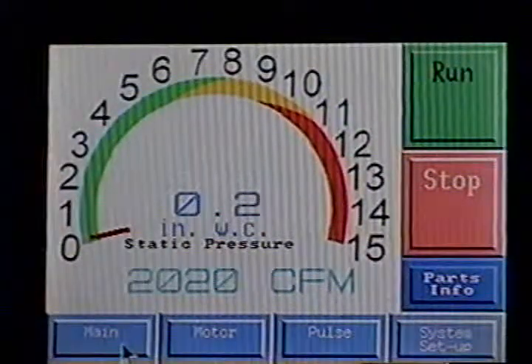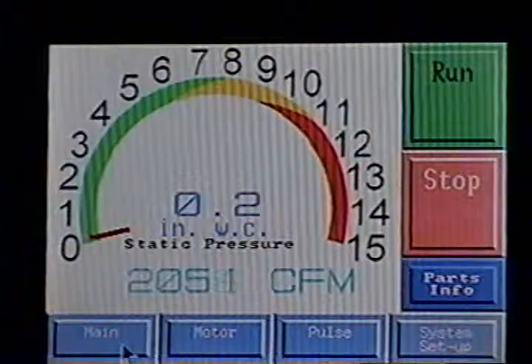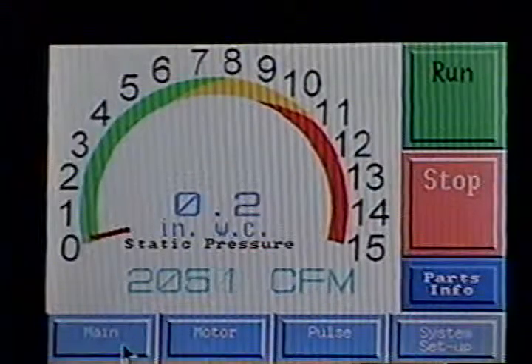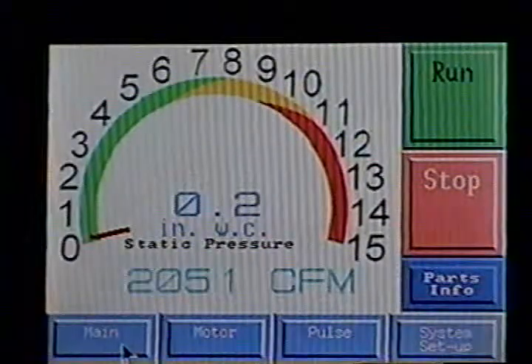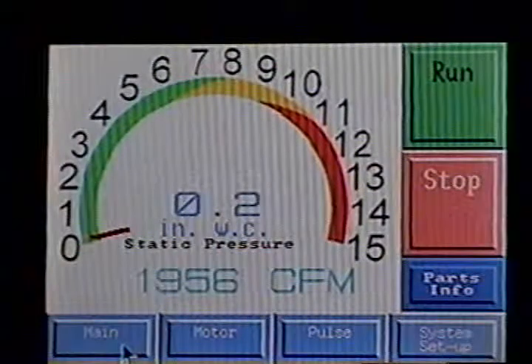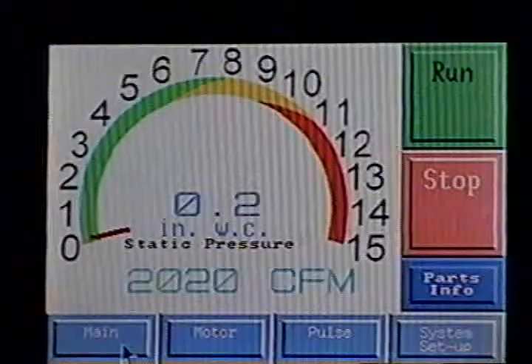Set of 2000. But it goes through and it monitors where it's at. I don't know how many of you can see it, but in the duct run behind the collector, the way we've chosen to do this is it has an orifice plate. It's a plate with some resistance. It's slightly smaller than the ductwork, and it measures the static drop across that plate. That's how it determines what the CFM is.